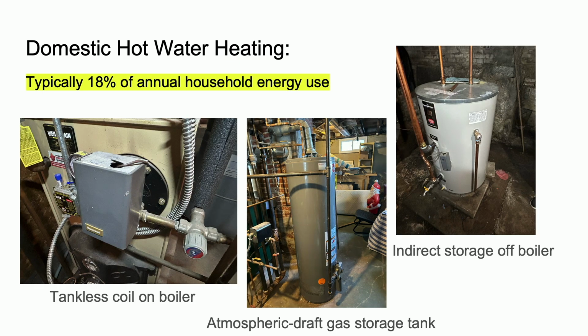Also, with tankless coils, besides inefficiency, the boiler is designed to provide forced hot water baseboard. That's what it does. And it can also give you a little bit of hot water while it's at it. But if you're in the shower enjoying a nice hot shower and the thermostat calls for heat, the boiler is going to prioritize the thermostat, and you're going to be cold in the shower. So you get really inconsistent temperature. It gets hot, it gets cold.